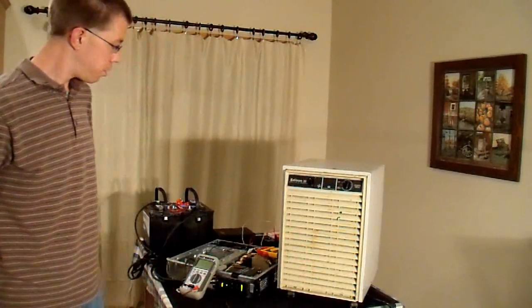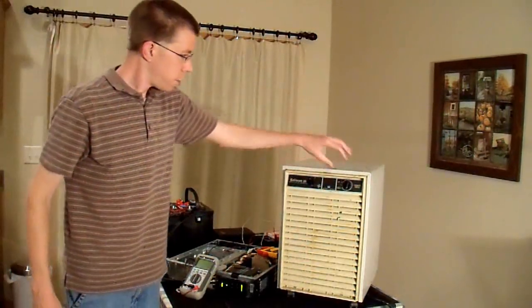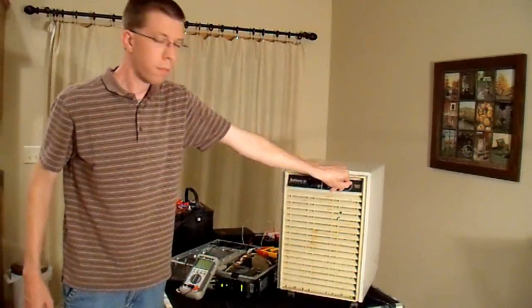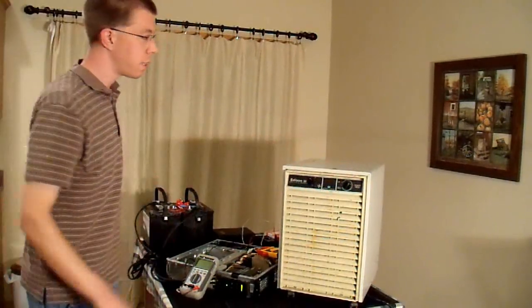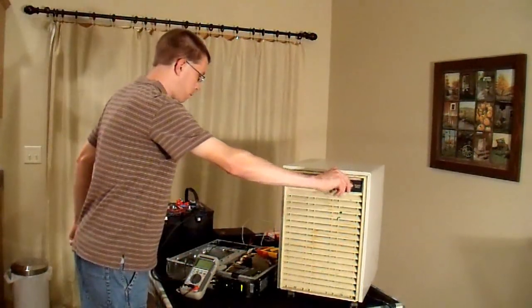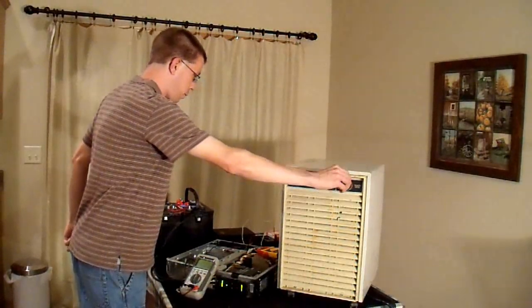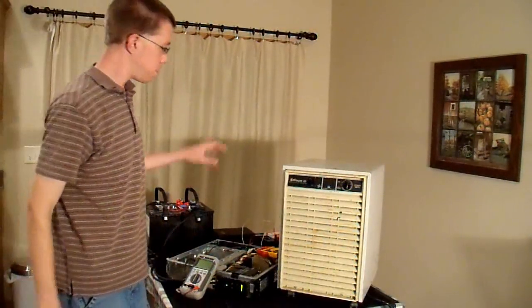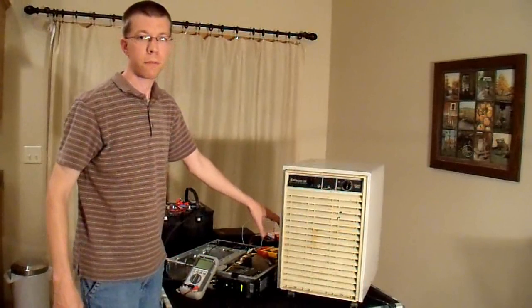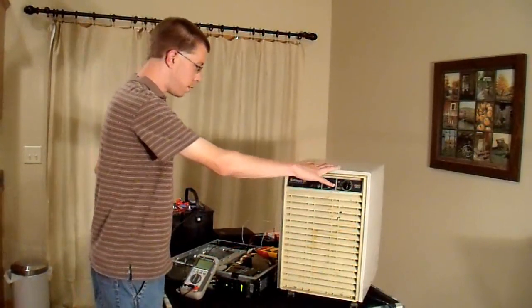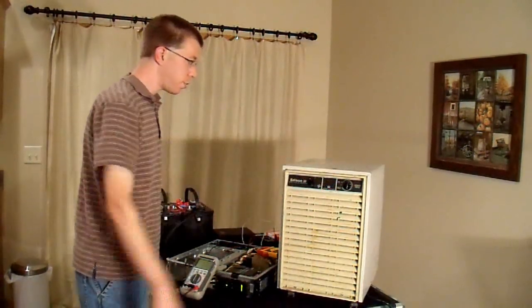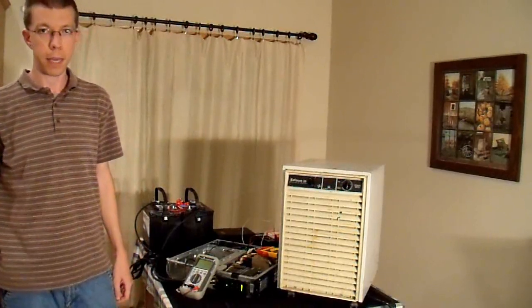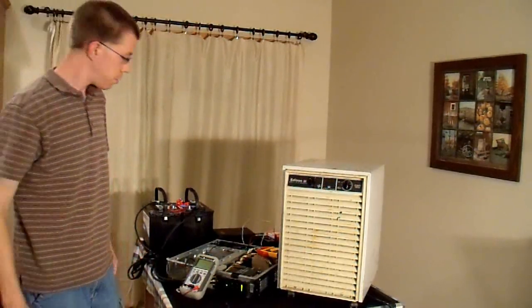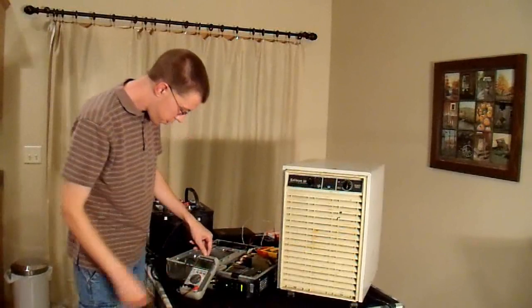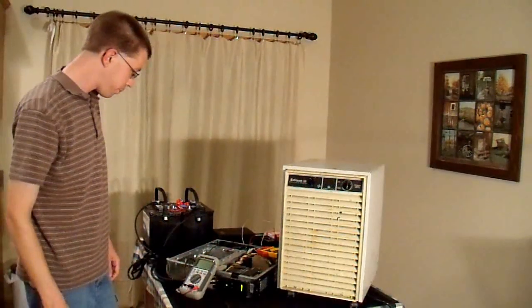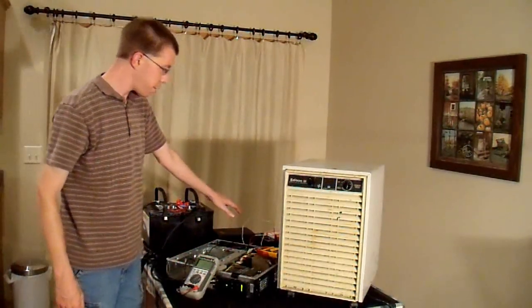So now what I'm going to do is shut off the unit, and I'm not going to wait for the pressure to equalize. I'm just going to turn it back on briefly, and my meter went up to 33 amps. So this particular dehumidifier takes 33 amps to start up. That's 33 amps at, let's check the voltage on that. I have my meter plugged right into the back of the UPS.